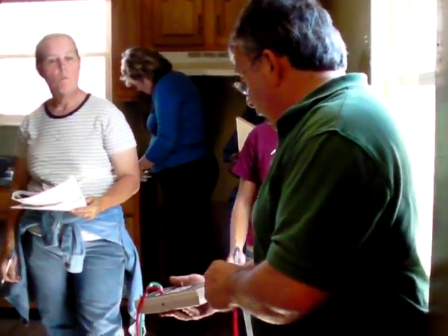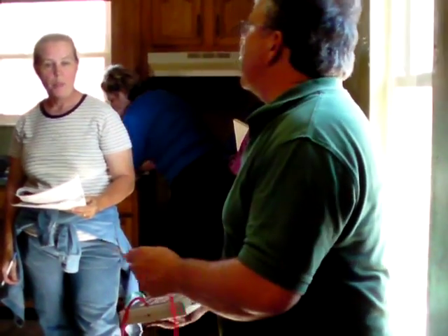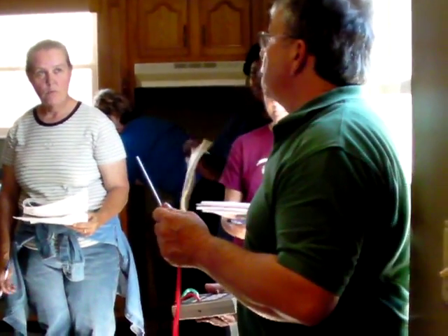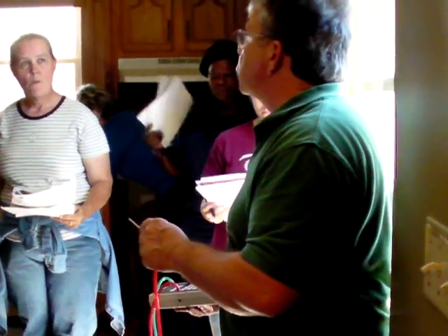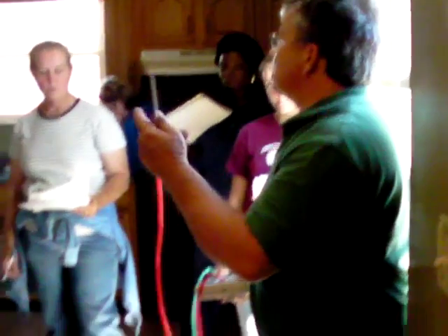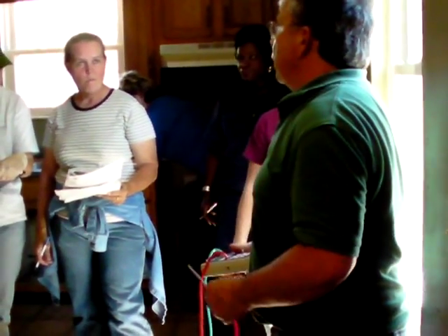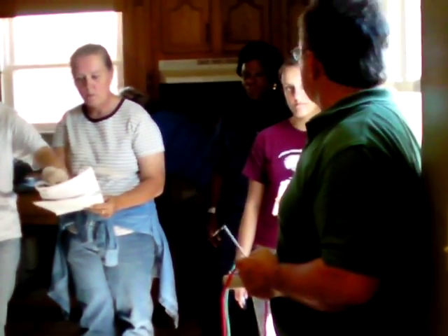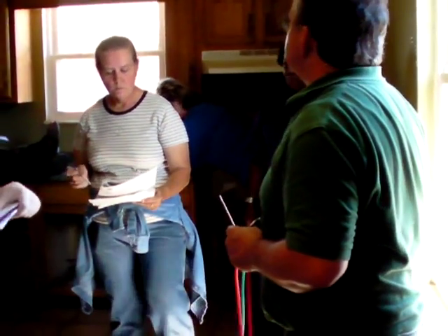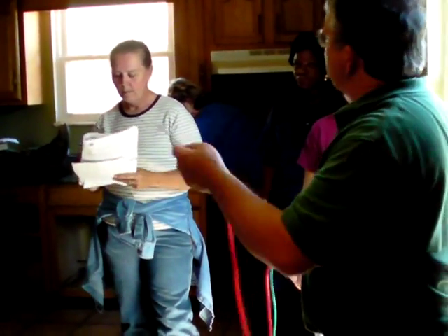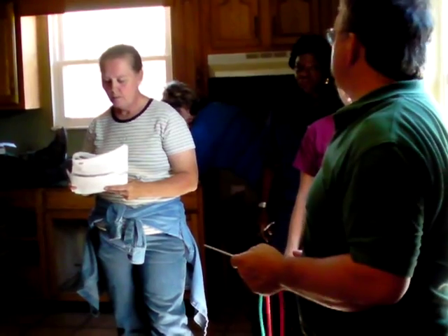But now, what would I do if I exceeded that -5 when I turn on all these fans? I'm going to shut them all off, and I'm going to mark down on my notes that it exceeded the CAZ depressurization limit, and that I'm going to do the tests under natural conditions. I know that's a mouthful. And don't do it under worst case. If I exceed that limit, I will not be doing it under worst case.